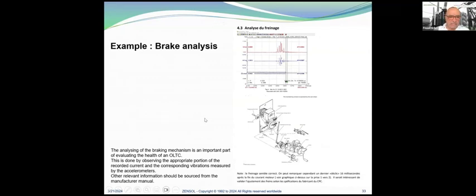Example. The analysis of the braking mechanism is an important part of evaluating the health of an OLTC. This is done by observing the appropriate portion of the recorded current and the corresponding vibration measured by the accelerometers, and other relevant information should be sourced from the manufacturer manual.